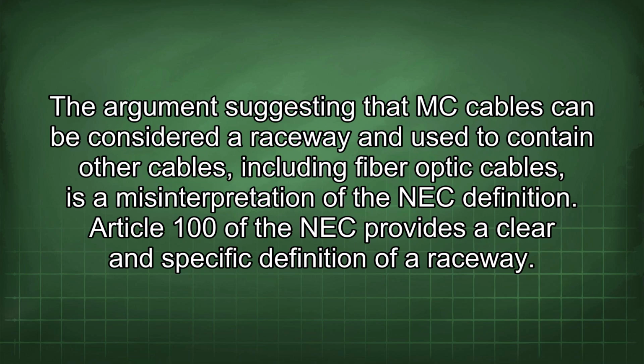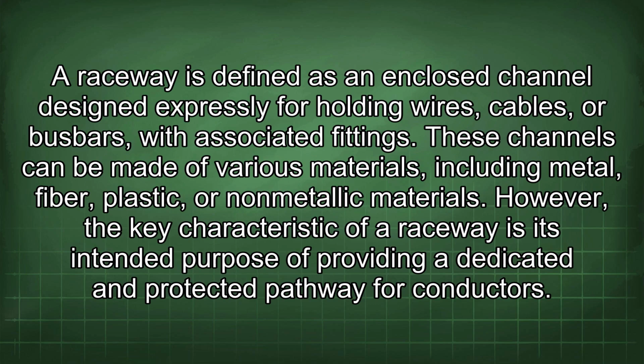The argument suggesting that MC cables can be considered a raceway and used to contain other cables, including fiber optic cables, is a misinterpretation of the NEC definition. Article 100 of the NEC provides a clear and specific definition of a raceway. A raceway is defined as an enclosed channel designed expressly for holding wires, cables, or busbars, with associated fittings. These channels can be made of various materials, including metal, fiber, plastic, or non-metallic materials. However, the key characteristic of a raceway is its intended purpose of providing a dedicated and protected pathway for conductors.